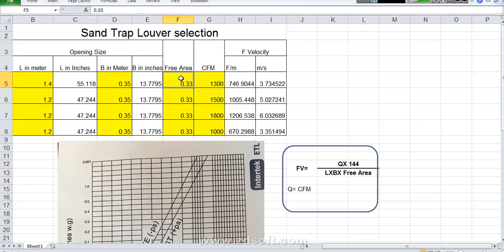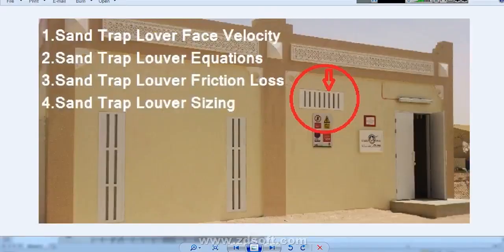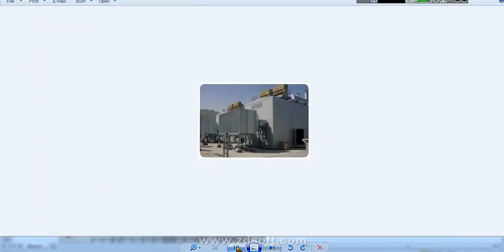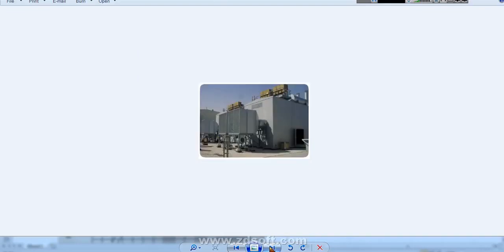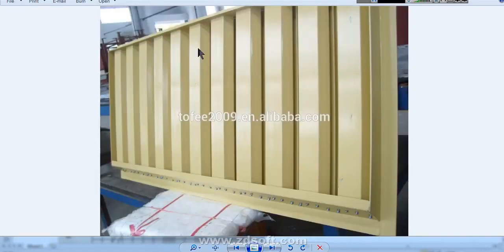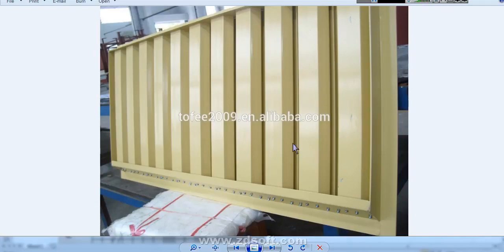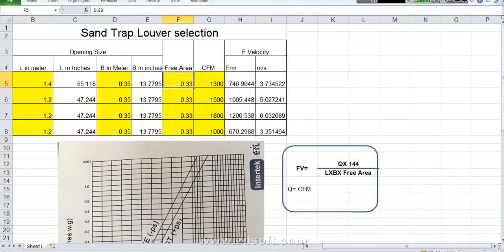And the free area of the Sand Trap Louver what it means. If you take one complete Sand Trap Louver like this, in this total area air will not pass. There is some percentages there like 50% air will pass or 30% air will pass or 20% air will pass. This free area you need to ask your manufacturer or supplier what is the free area you are supplying Sand Trap Louver.